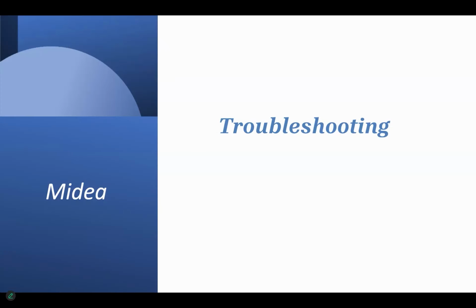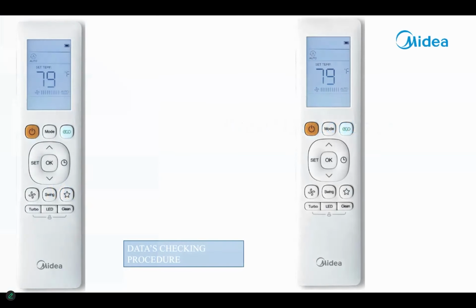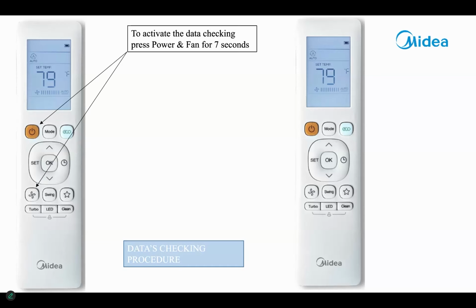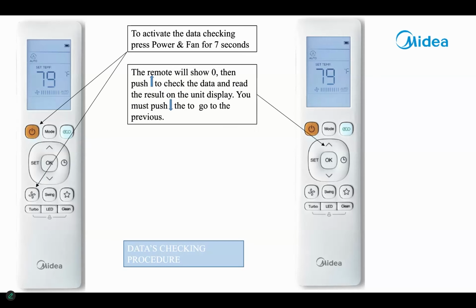All right, so let's talk about some troubleshooting here. Let's talk about the data. Let's talk about data checking, where you can actually pull operational parameters on it while it's running. This data checking mode you can do anytime, whether the unit's running, off, just the fan running, it doesn't matter. So you can pull this information anytime. What you're going to do is take the handheld remote and point it at the display on the AHU. You're going to press and hold the power and the fan buttons for 7 seconds. When you do that, it's going to show 0 in the display on the remote, and it'll show NA on the AHU display.